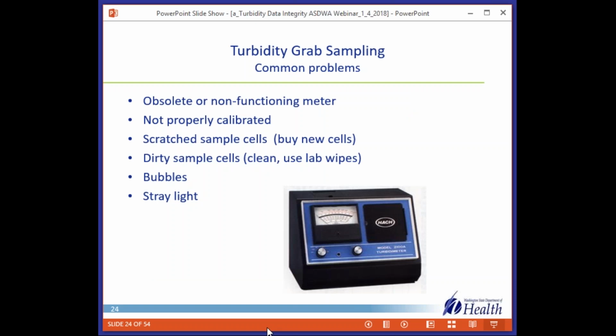When we talk about verification, we're usually talking about grab sampling and this difference between the grab and the online. So I just want to review some of the common problems we've been finding. One is obsolete or non-functioning meters. Wow, our industry, I think probably especially operators, we're a frugal group. They want to get the most out of all the money they collect from people and use to run these plants. And sometimes they may be holding on to equipment a little too long. Not properly calibrated, another common problem. Back to the frugal nature: scratched sample cells are tough, so buy some new ones.